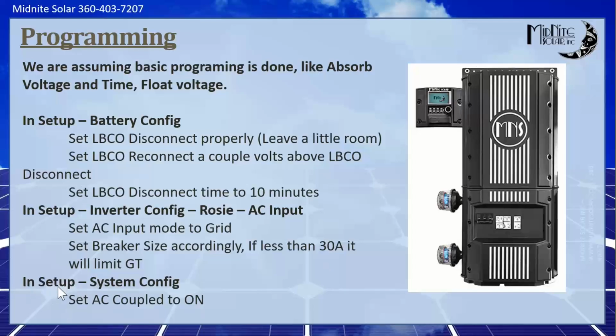In the system setup, so setup button, system config, and then we scroll down and turn AC coupled to on. What that's going to do is frequency shift. What the Rosie does is follow a fairly prominent UL 1741 SA/SB type curtailment, if you will. It frequency shifts up into the 62 hertz range to curtail the grid tie inverter. So if you have a grid tie inverter that is capable of 1741 SA or SB, the Rosie can throttle it back. I believe it's 4 steps.